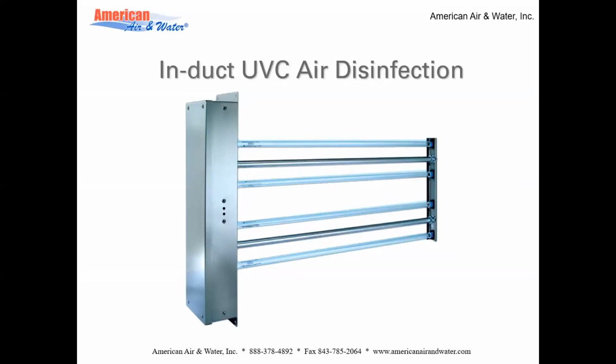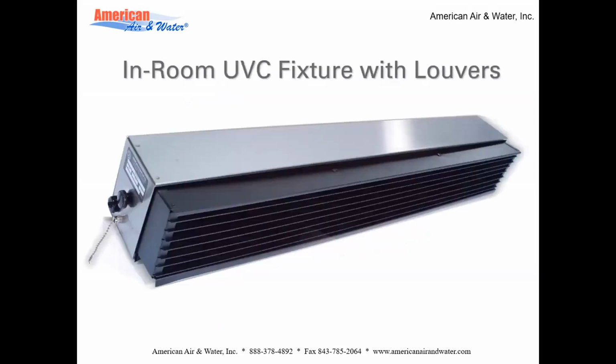This is an example of UV fixture that goes inside the air ducts to disinfect the airstream. Only the UV lamps and their supports are inserted in the air duct, and the chassis of the fixture stays on the outside. And this is a relatively easy installation. The only downside is it does not shine directly on the coil, so it does not disinfect the coil.